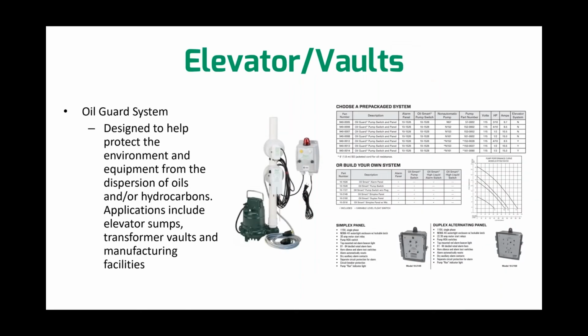So the next thing is the elevator and vault system, what we call our Oil Guard system. We offer it in a few different ways. We have prepackaged systems, which you'll see over here to the right on the chart, or you can build your own system where you pick the pump, pick the switch, pick the alarm panel, or pick the pump and then get a control panel, whether it's simplex or duplex, where simplex is 1 pump, duplex is 2 pumps. But these Oil Guard systems are designed to help protect the environment from any oils or hydrocarbons going out into the system wherever it's going. Again, applications that we already talked about: elevator sumps, transformer vaults, and use in numerous manufacturing facilities.